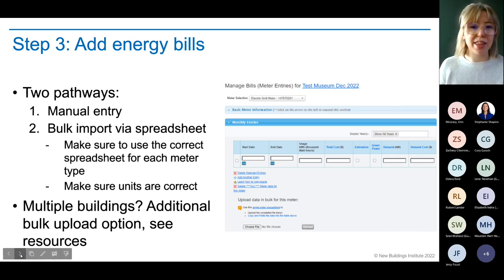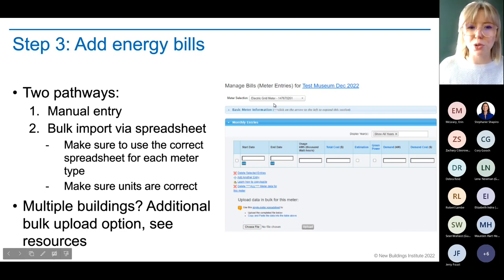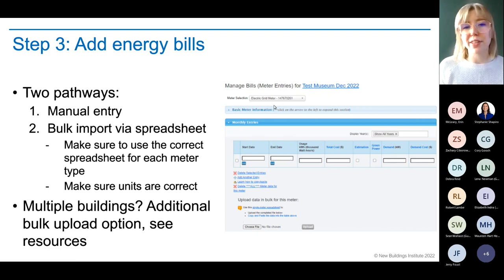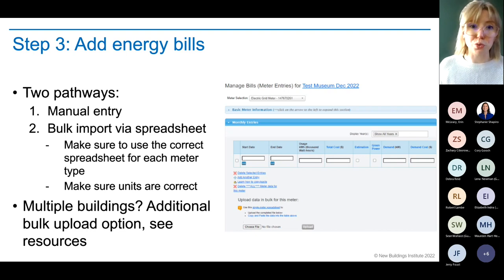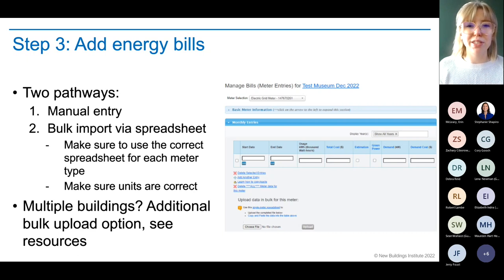We're on step three — adding energy bills. There are two different ways to do this. The first is manual entry. You fill in the start date, end date, and usage. The cost field is optional — shown in blue — while start date, end date, and usage are required fields shown in black font. If it is an estimation, you need to check that box, but for this project we want actual real data. You can also forecast and estimate consumption for future periods if needed.